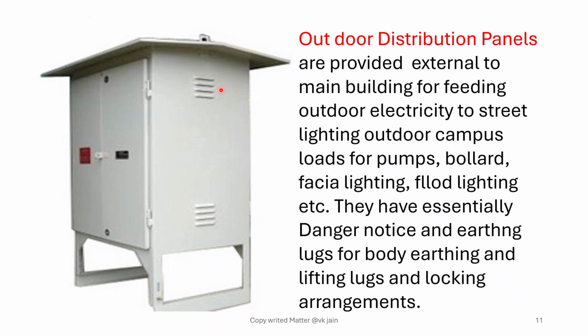The slide shows a figure of outdoor distribution panels which are provided external to the main building for feeding outdoor electricity to street lighting and outdoor campus loads for pumps, bollards, facade lighting, flood lighting, etc. They have essentially a danger notice board and earthing lugs. This danger board and earthing lugs are provided on this side here, this side and that side. They also have earthing lugs for body earthing, lifting lugs and locking arrangements. The lifting lugs and this is the locking arrangement.